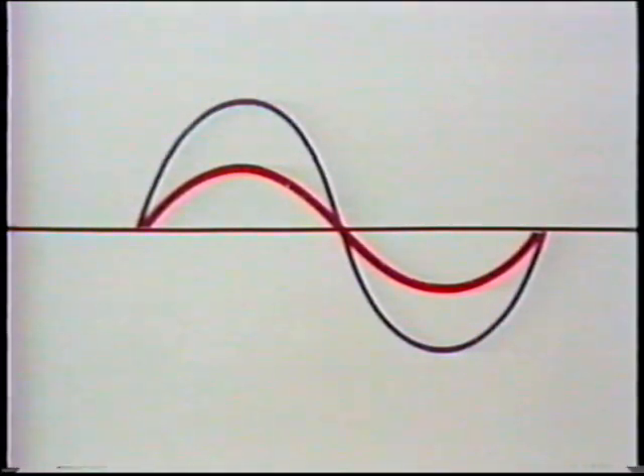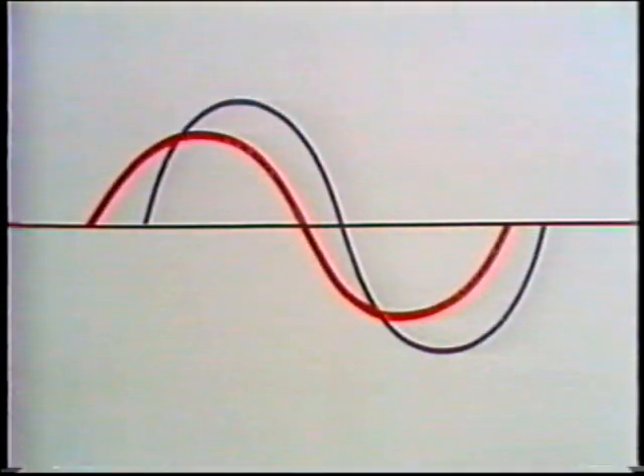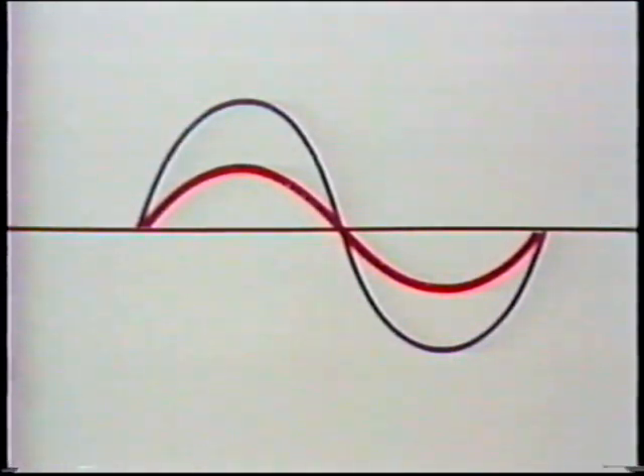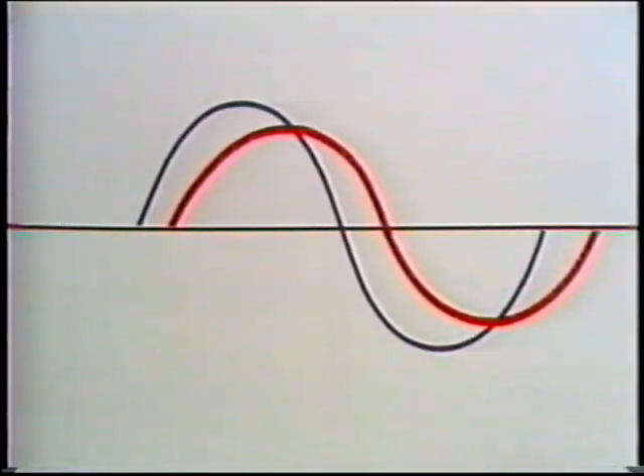Now, if the current flowing through the rotor windings is increased, current and voltage in the stator go out of phase. The current cycle starts a little sooner than the voltage cycle. This causes current flow in the stator to go up, and the motor operates less efficiently. If current flowing through the rotor windings is decreased, the stator's current cycle begins a little later than the stator's voltage cycle. Current flow through the stator increases, and the motor again operates less efficiently. As we're going to show you, this phenomenon can be used to improve the electrical efficiency in your plant. But first, let's take a look at a demonstration of this effect on an actual synchronous motor.